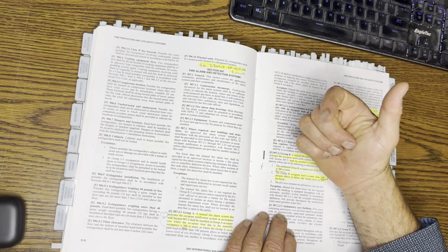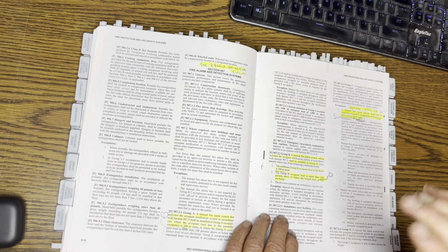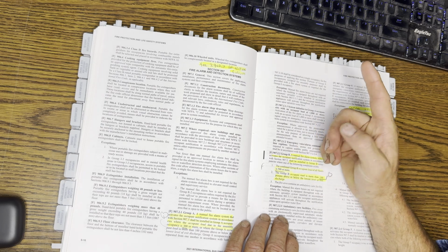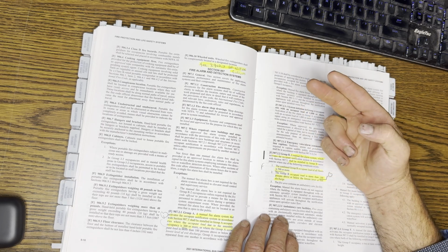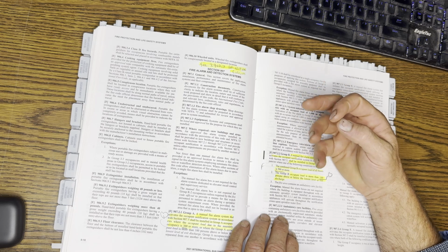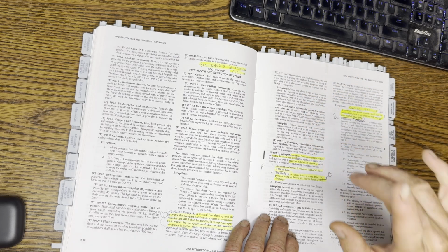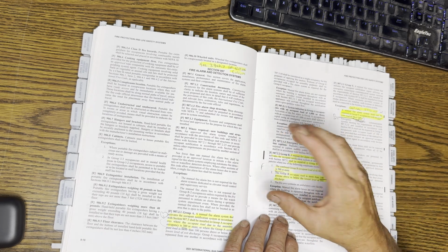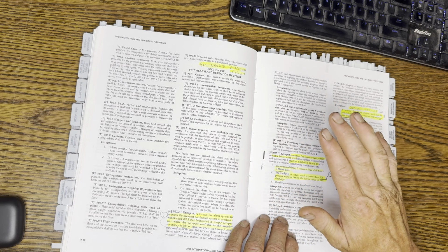Keep this in mind. There's two kind of fire alarms. There's manual, which you have those pulls, right? And then they sound, signaling devices go off throughout the building, notifying personnel to evacuate. So that's one type of a fire alarm system. The other type is an automatic system. So an automatic system would be like smoke detectors tied into a fire alarm system. I want to be clear, that is not the same thing as the standalone fire alarm systems in a house. Okay, I'm talking about something totally different.